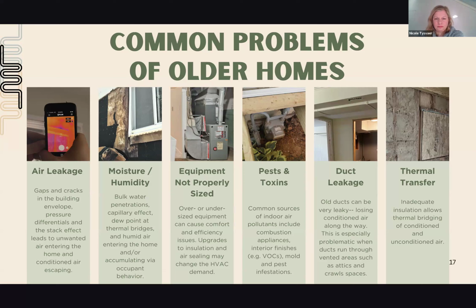And when you do, if you're using the existing ductwork, you want to make sure that ductwork is sized as well, because you're going to lose or gain static pressure, and that equipment is not going to work the way you want it to. And then there's duct sealing, AeroSeal. AeroSeal is a very good duct sealing system. When you get the old unit out, you can seal that duct and then put your new unit in to get your duct sealing done.